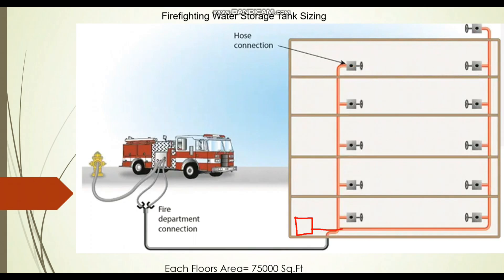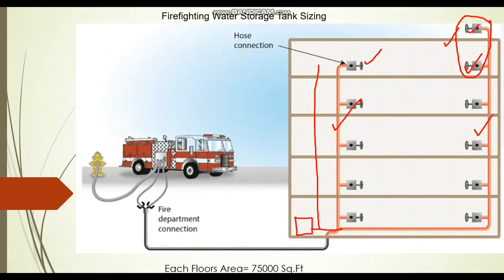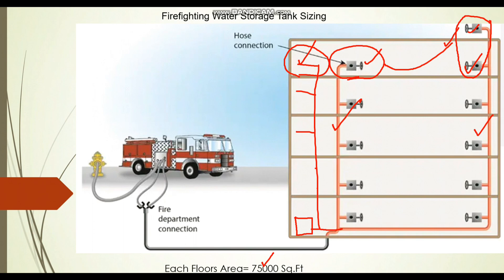Now consider a third condition for the same project: we have the last standpipe, a second standpipe, and one additional standpipe — three total. The remote standpipe is the same: 500 GPM (250 plus 250). For the second standpipe, with our floor area of 75,000 square feet, we consider one landing valve: 250 GPM, giving 750 GPM cumulative. For the third standpipe we also consider only one residual landing valve at 250 GPM. So total is 500 plus 250 plus 250 = 1000 GPM.